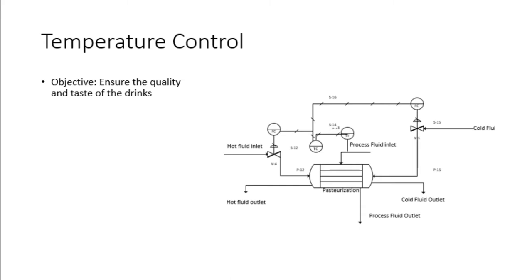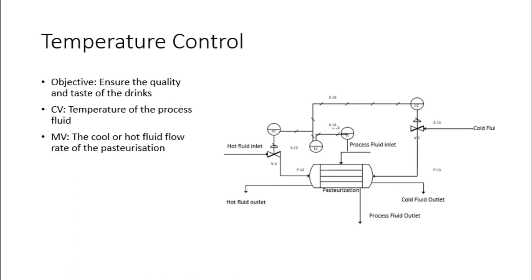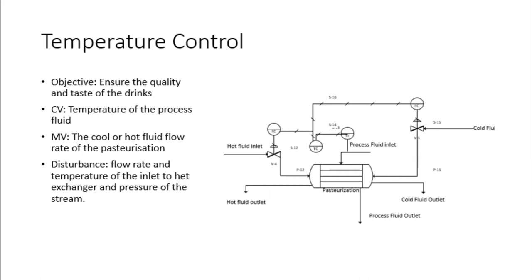Next, we will talk about the temperature control in the pasteurization. The objective of this temperature control is to ensure the quality and taste of the drink. This is because some ingredients may only dissolve at a specific temperature, and too high a temperature in the solution will cause the CO2 content to decrease. To control the temperature, a feedback system is used. The transmitter will detect the minimum and maximum temperature of the solution at the inlet of pasteurization and send a signal to manipulate the flow rate of cold and hot fluid using a flow rate controller. The flow rate controller will control the valve for hot fluid and cold fluid. The disturbance of this control is the flow rate and temperature of the inlet stream and also the pressure.